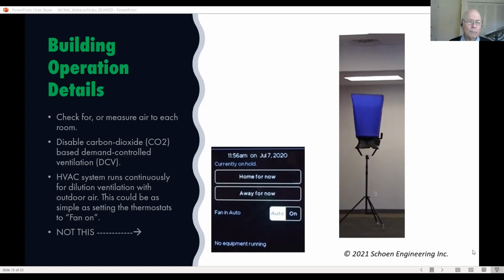We talked about the second bullet, disabling carbon dioxide demand controlled ventilation. You want to have more ventilation now during a pandemic, and see that the HVAC system really runs continuously. So I should have put a big red line through this, as I have on some of my other slides. You do not want fans in auto, and if it's pulling in outdoor air and it's filtering air, we want that system running constantly and not turning on. We don't want the fan turning on and off based on a thermostat. You may want the heating and cooling action turned on and off, yes, to maintain comfort conditions, but not the fan if it's pulling in outdoor air and it's doing dilution and filtration.